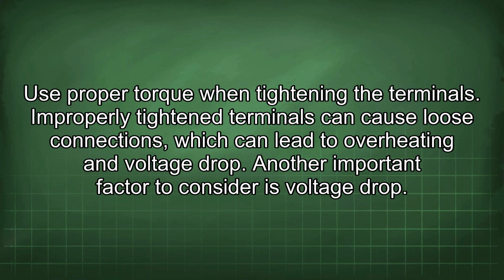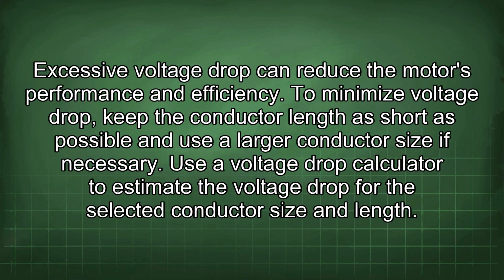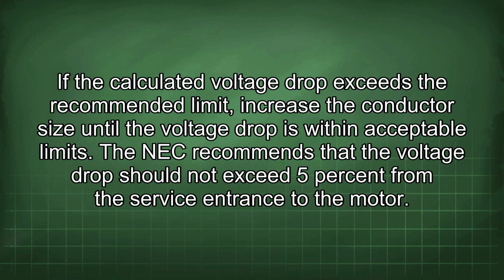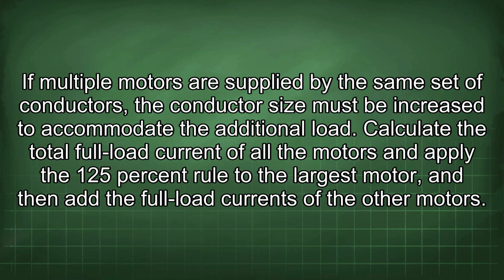Another important factor to consider is voltage drop. Excessive voltage drop can reduce the motor's performance and efficiency. To minimize voltage drop, keep the conductor length as short as possible and use a larger conductor size if necessary. Use a voltage drop calculator to estimate the voltage drop for the selected conductor size and length. If the calculated voltage drop exceeds the recommended limit, increase the conductor size until the voltage drop is within acceptable limits. The NEC recommends that the voltage drop should not exceed 5% from the service entrance to the motor. If multiple motors are supplied by the same set of conductors, the conductor size must be increased to accommodate the additional load.